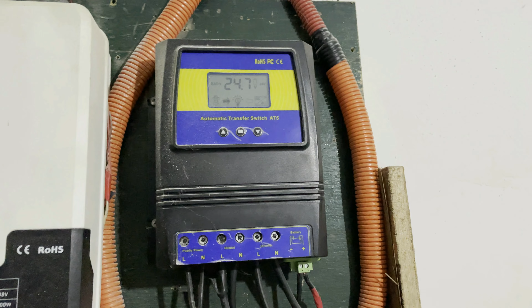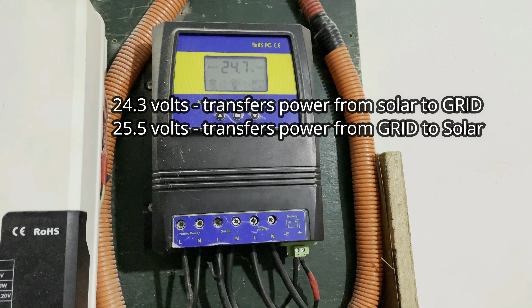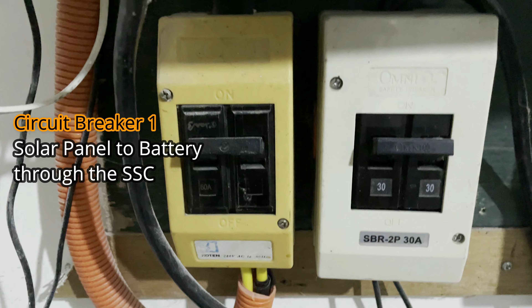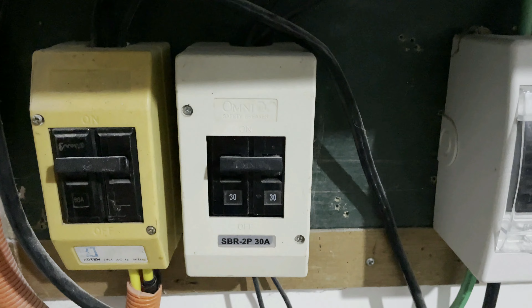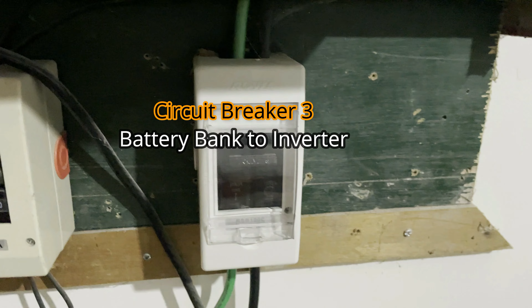I set it to transfer to the grid when the battery voltage is less than 24.3, around 7 or 8 in the evening, and switch back to solar when the voltage is at 25.5, usually around 7 in the morning. Next are the circuit breakers. This one cuts the power from the solar panel to the battery. The middle circuit breaker cuts the power from the battery to the automatic transfer switch. And the third one cuts the voltage from the battery to the inverter.